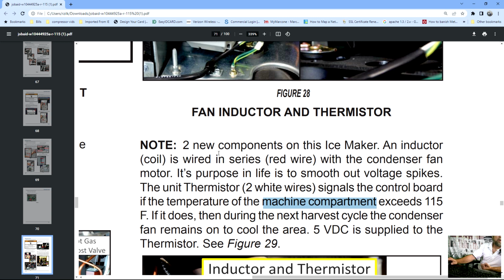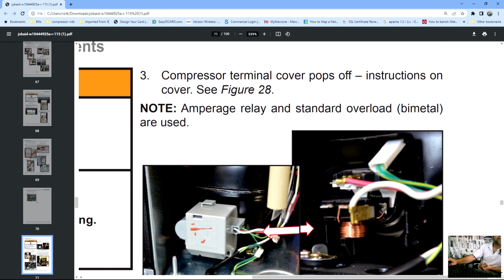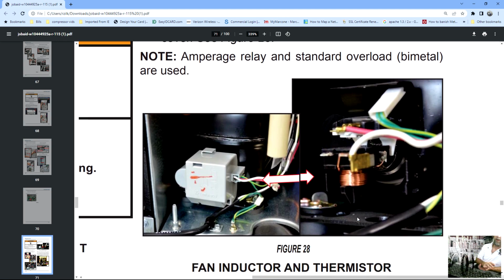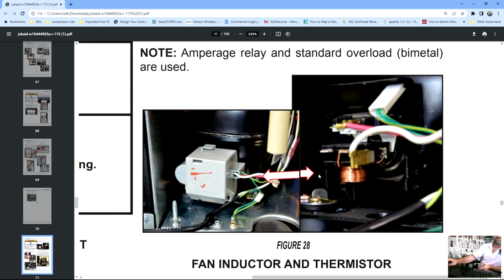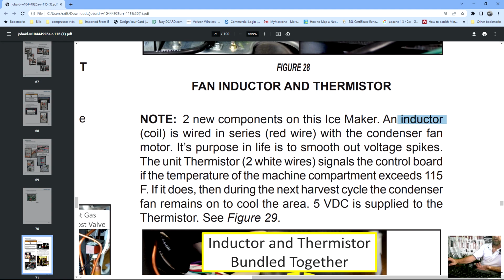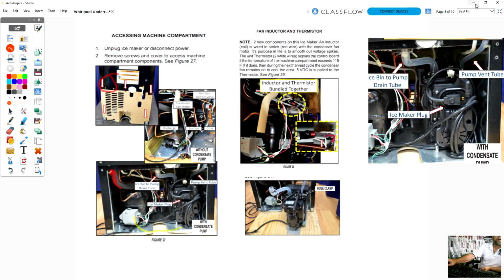and the other component in there is called an inductor. All that is basically a way to control the voltage going to the condenser fan. I did not look at this. Well, I'll look at the schematic with you. I think it's a variable speed condenser fan motor, and to help control the voltage going to that motor, they just added an inductor coil. I've never really seen many of them added, so they might have had a problem with voltage spikes coming from the board or something, that they went ahead and added this in just in case. I don't think it's a mandatory thing that has to be in there, but if it failed, your condenser fan would not run, and I'll show you that in the schematic.